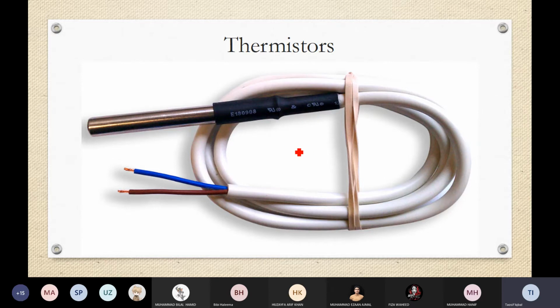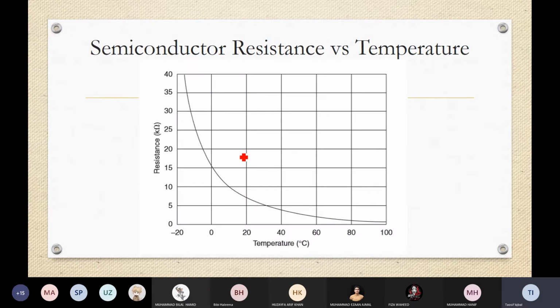So this is how a thermistor looks. Again, we have a protecting housing which protects the thermistor. So the thermistor is inside the metallic tube so that it can be used for a longer duration, and then the wire electrical connection is there to measure the change in resistance when there is temperature on the other side. So this is a typical resistance versus temperature curve, and depending upon the certain temperature, we can find out the resistance.